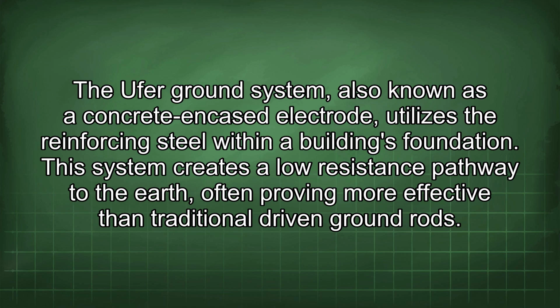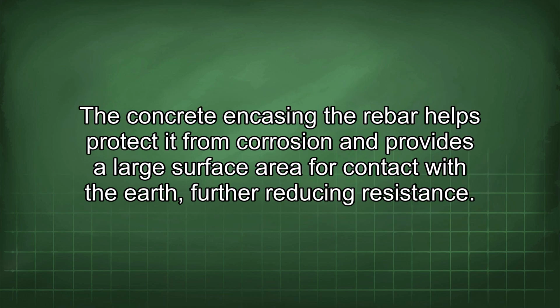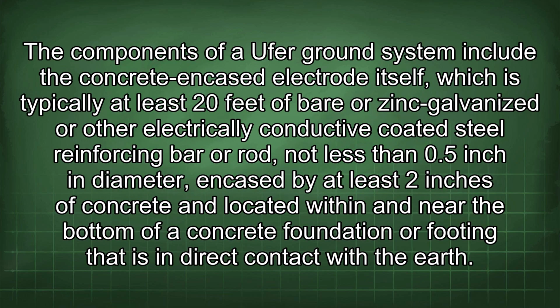This system creates a low-resistance pathway to the earth, often proving more effective than traditional driven ground rods. The concrete encasing the rebar helps protect it from corrosion and provides a large surface area for contact with the earth, further reducing resistance.